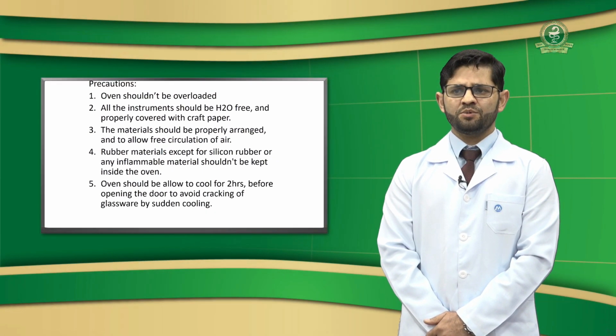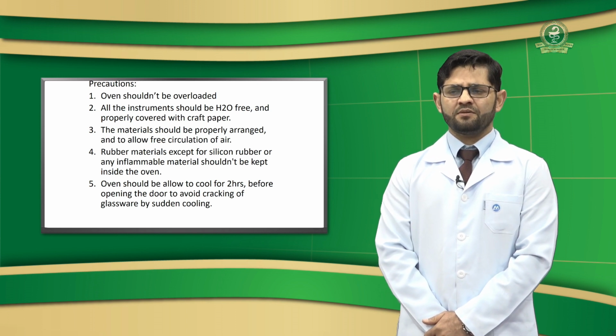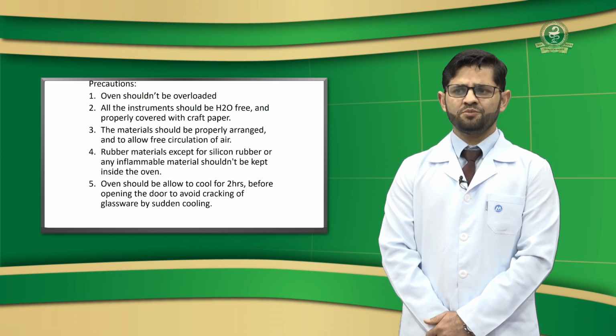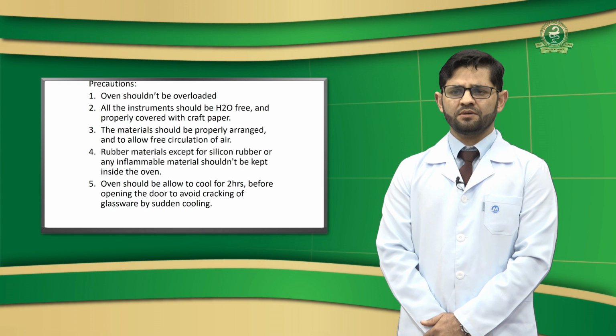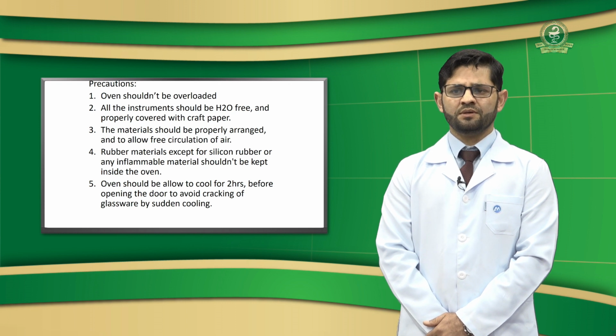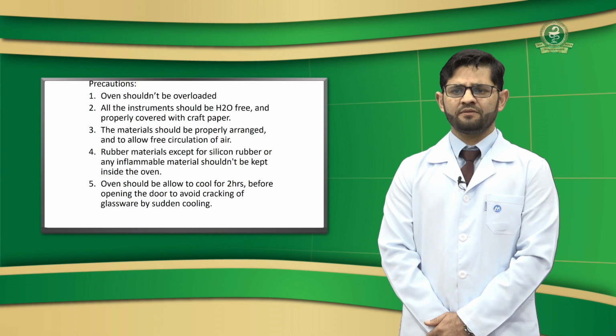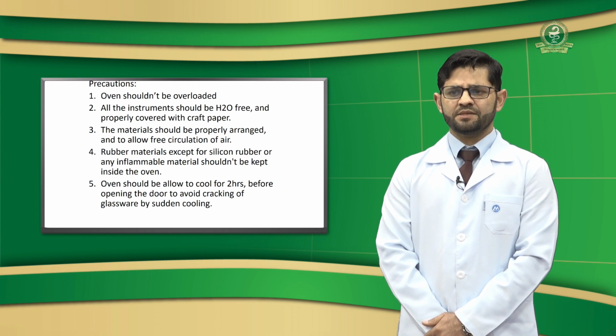Fourth, rubber material, except for silicone rubber, or any inflammable material shouldn't be kept inside the oven. Fifth, the oven should be allowed to cool for 2 hours before opening the door to avoid cracking of glassware by sudden cooling.